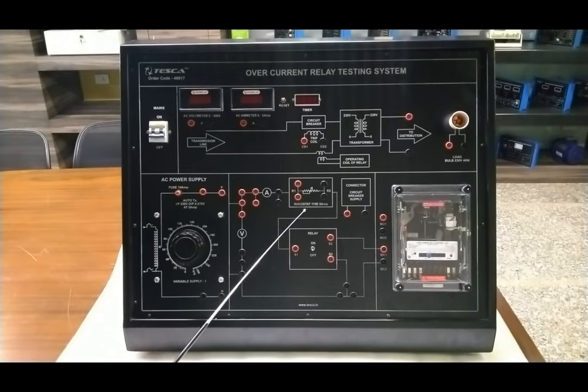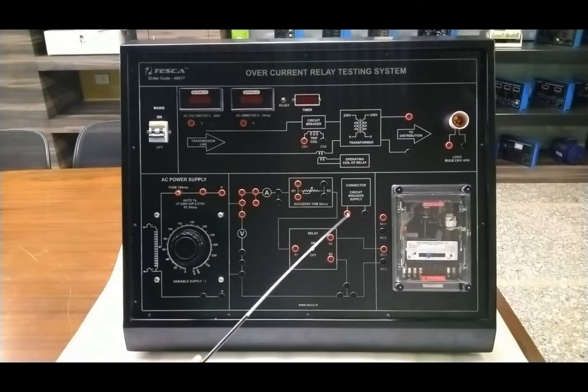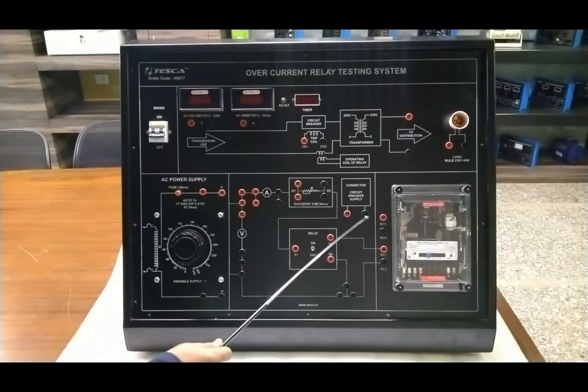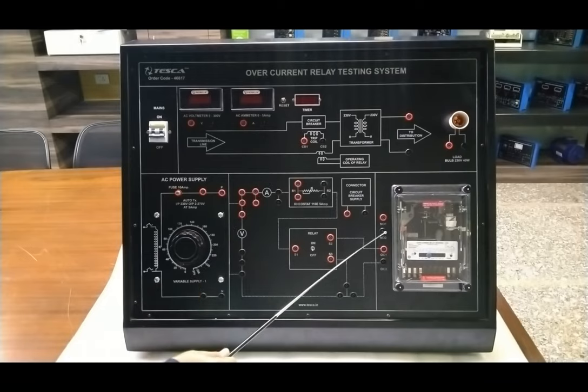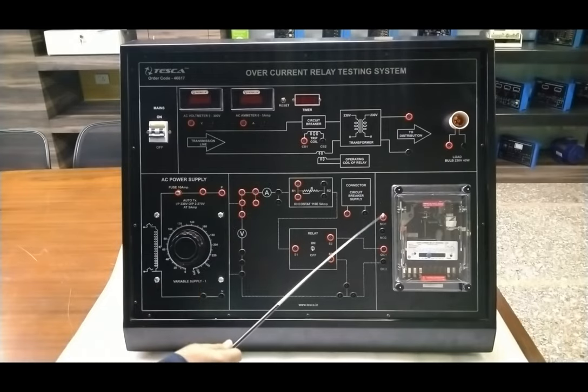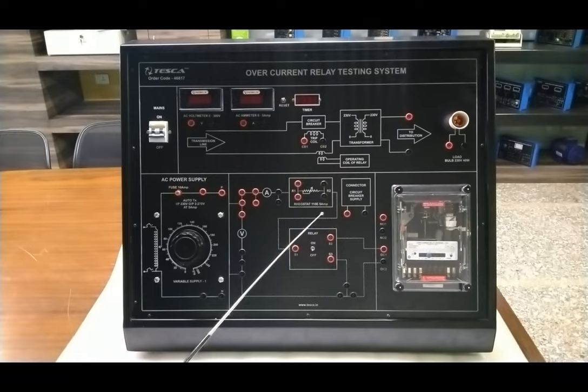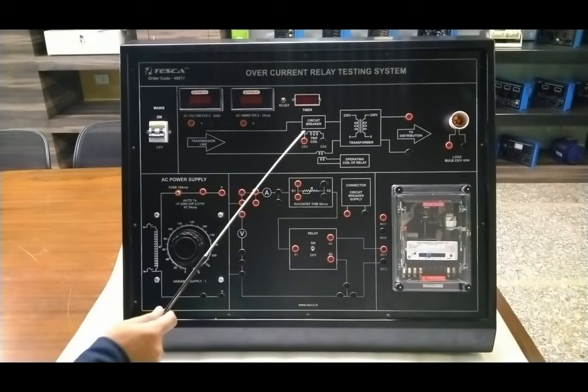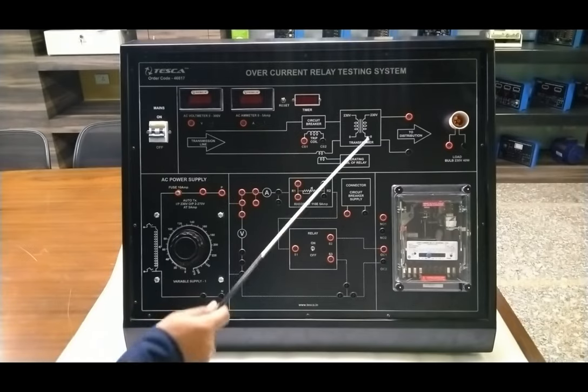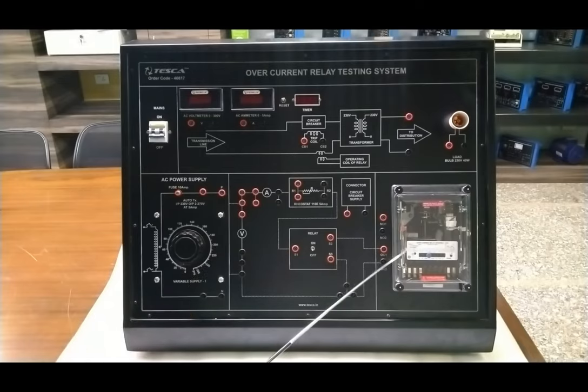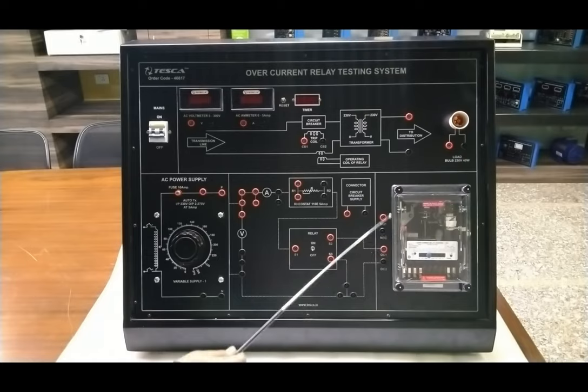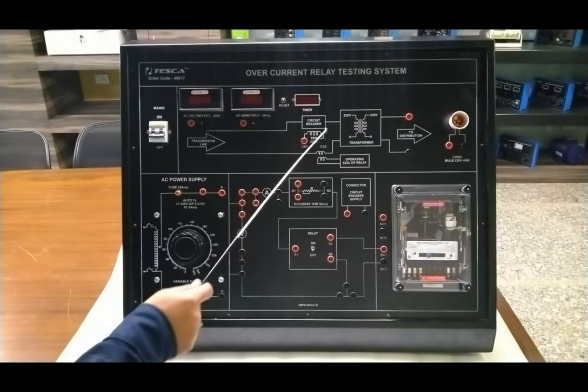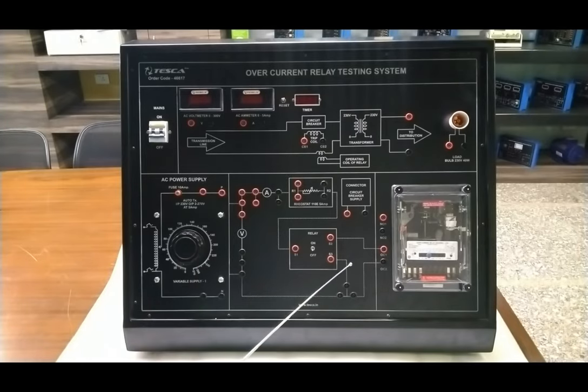A connector for the circuit breaker supply is provided here. This will be directly going through the normally open terminal of the contactor — the contactor is behaving like the circuit breaker here. So the circuit breaker will be connected when the supply is continuously on, and when the current exceeds the set value of the IDMT relay, the NO terminal of the overcurrent relay will change to NC and an open circuit will occur, so the circuit breaker will open and the load will be cut off from the complete transmission line.